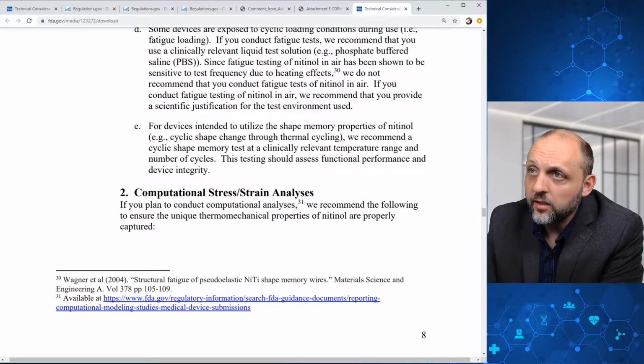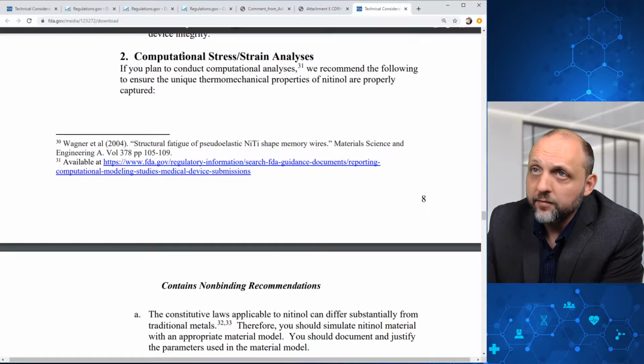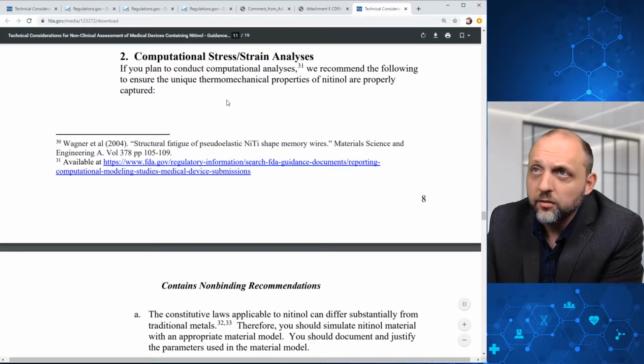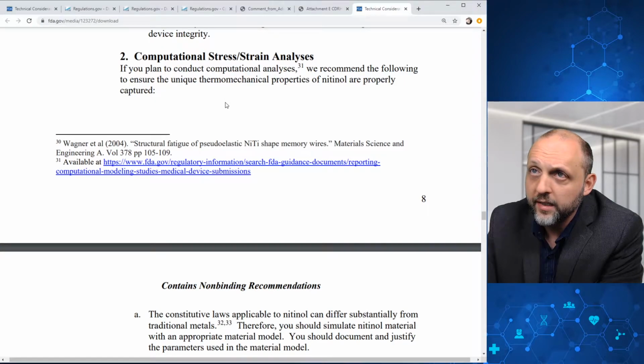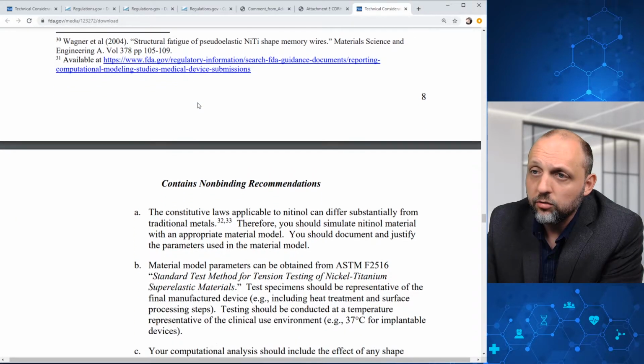And for devices intended to utilize the shape memory properties of nitinol, FDA recommends a cyclic shape memory test at a clinically relevant temperature range and number of cycles. And then FDA gives some additional details here in terms of computational stress or strain analyses. If you plan to conduct computational analyses, you should follow these recommendations here.